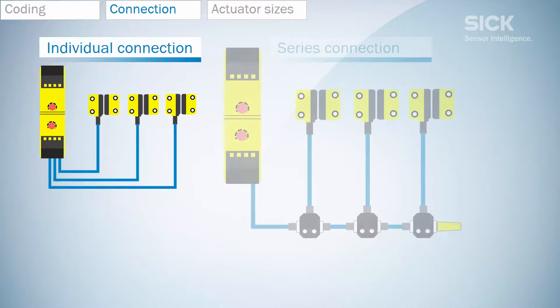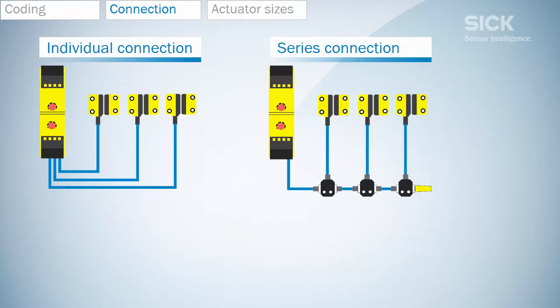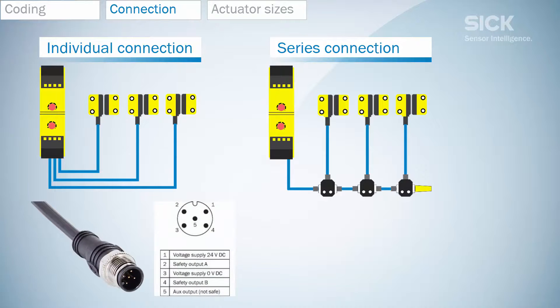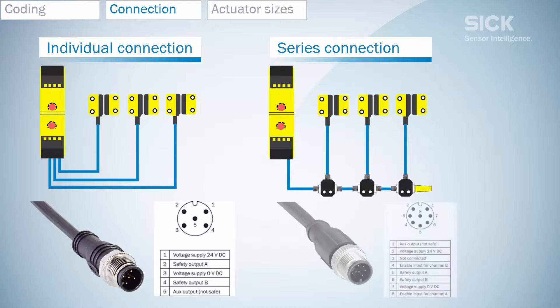Every sensor can be connected either individually or in series. Therefore, there are different connection options available: M12 5-pin connector, or 5-wired cable for individual connection, or M12 8-pin connector with two additional inputs for series connection with T-junctions.